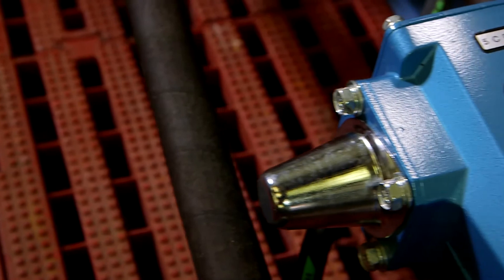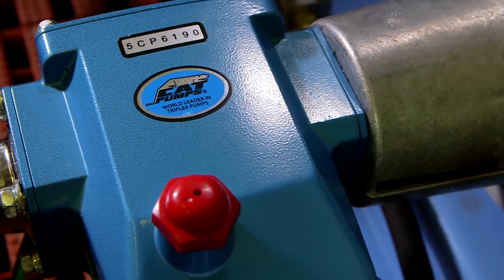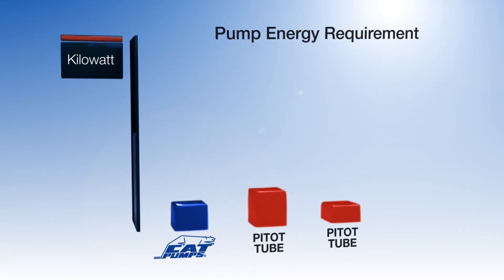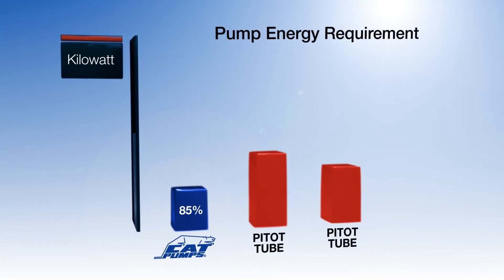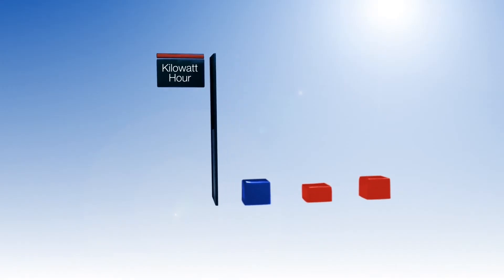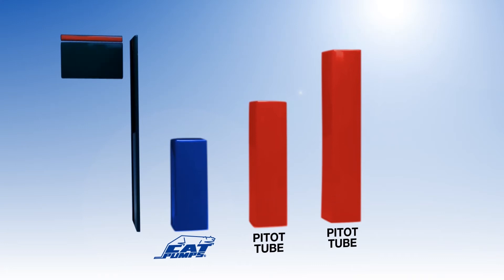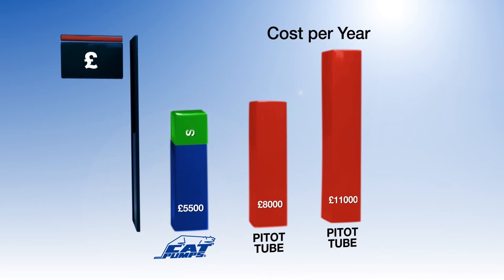Here's how Cat Pumps' WashSaver system can produce significant energy and cost savings. Because Cat Pumps are 85% efficient, compared to pitot tube centrifugal pumps at only 60 or 45% efficient, the motor's energy requirements are much lower. A typical week's energy consumption for a wash-down application shows how Cat Pumps use far less energy than pitot tube centrifugal pumps. Converting these to annual costs, savings can be 50% over a pitot tube centrifugal pump system.